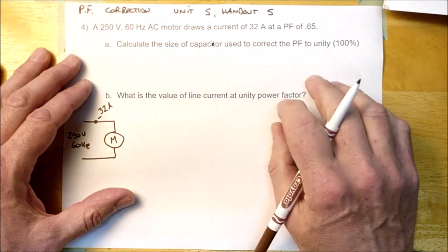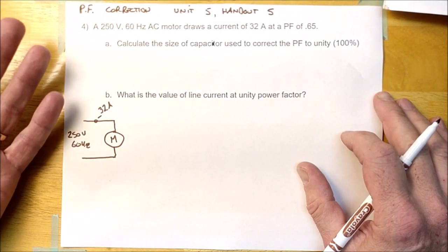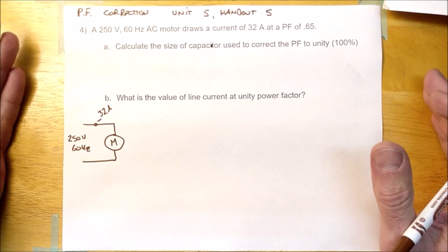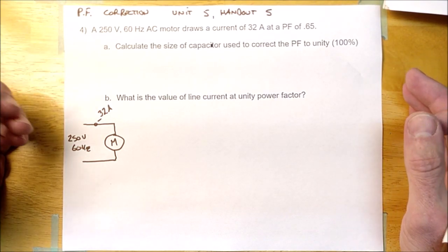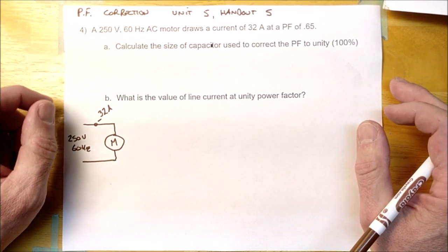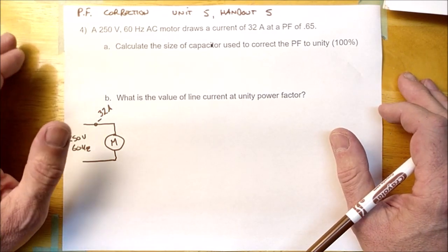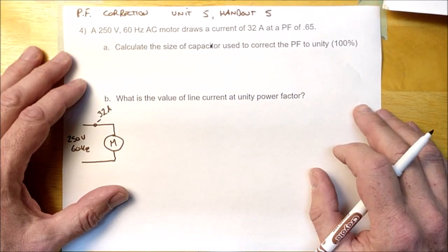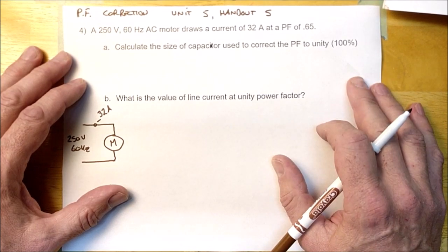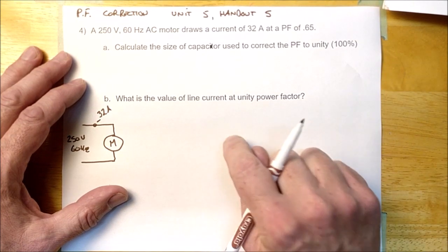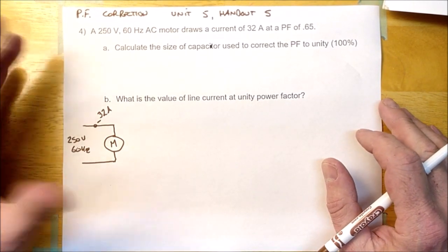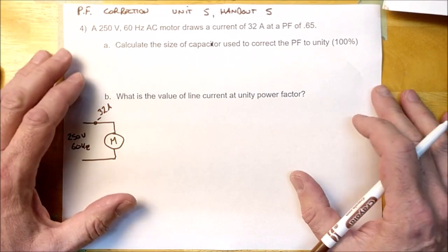So when we do power factor correction, we're going to be taking inductive loads and adding capacitors to them in parallel in order to improve their power factor either to unity — meaning the power factor is 1 and the phase angle is 0 — or we're going to correct loads to 90%. Those are the two power factor correction types we're going to cover. We're going to start with correcting a circuit to unity, and then we'll also learn about correcting the power factor to 90%.